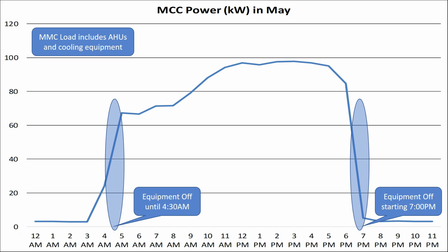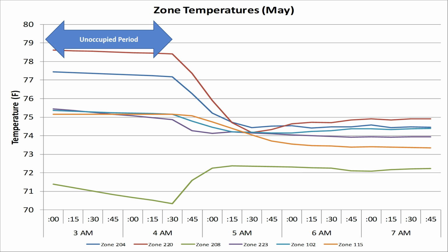To estimate optimal AHU start time, several zones that were termed as important were identified to be monitored. These zones included a mix of internal zones that were in constant need of cooling, such as the copier room as well as offices of senior executives.